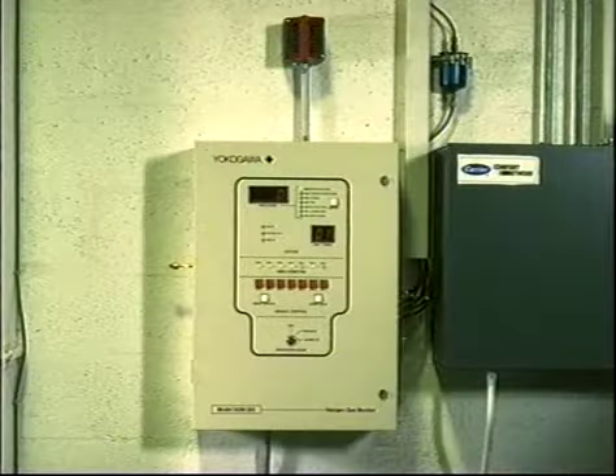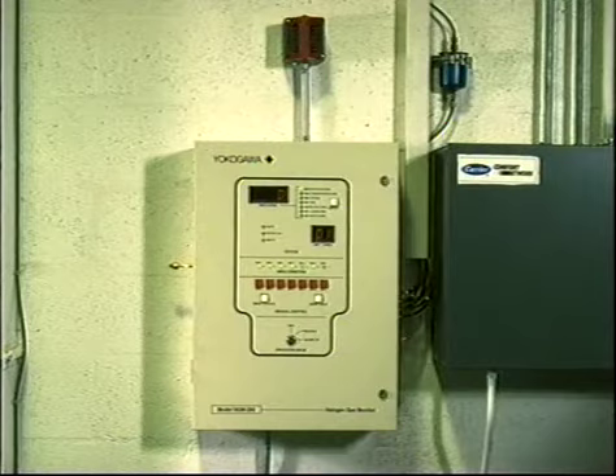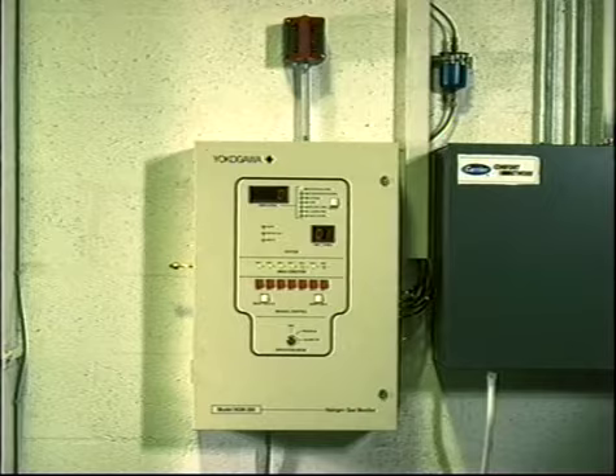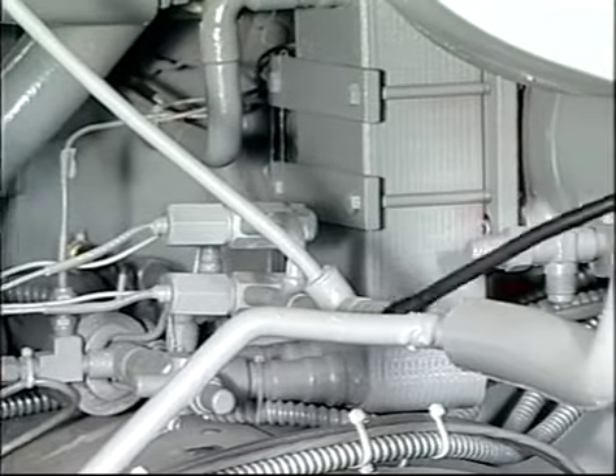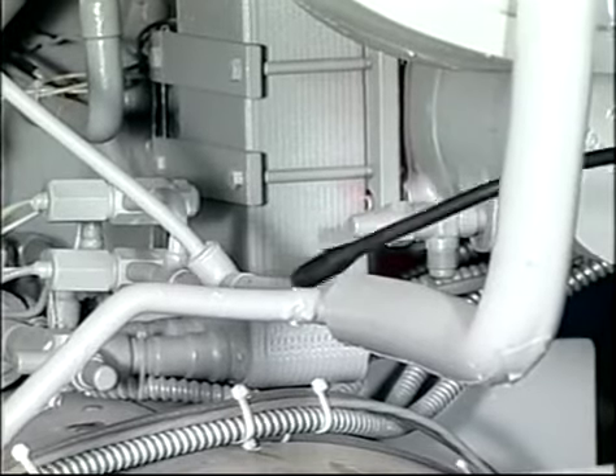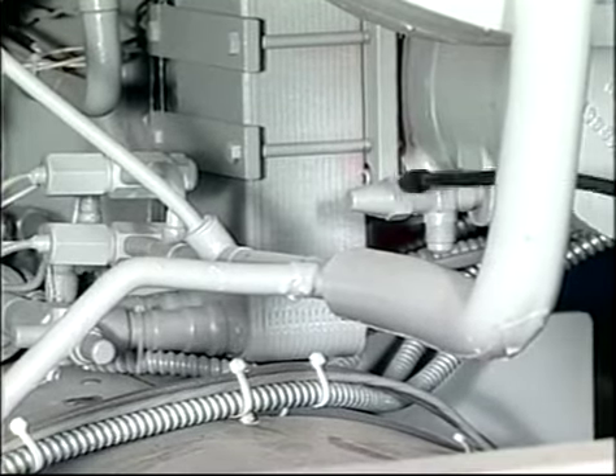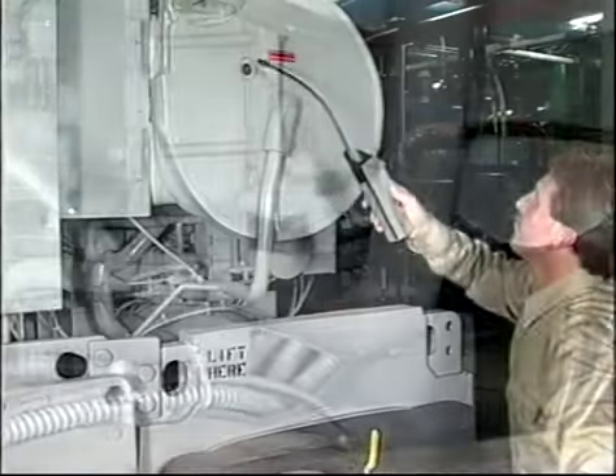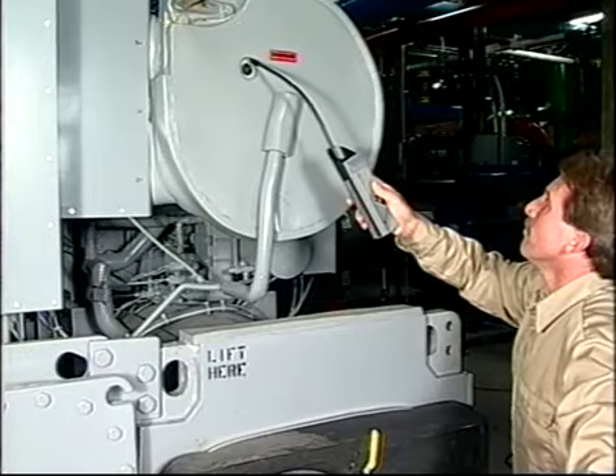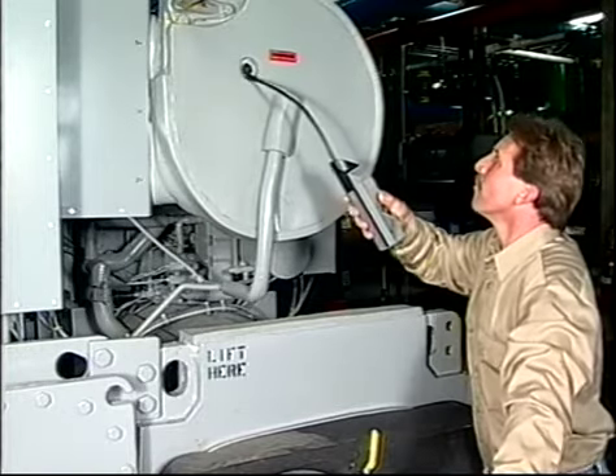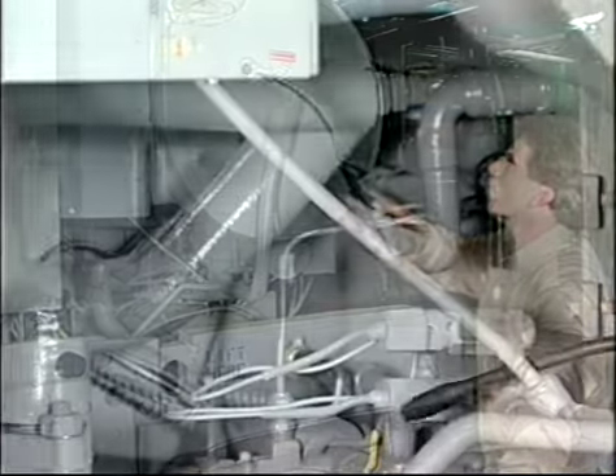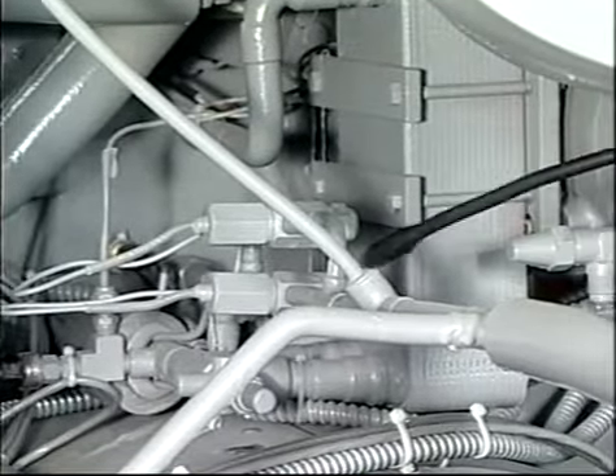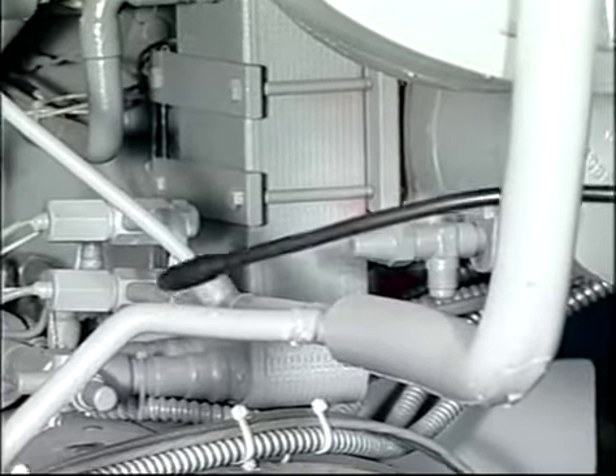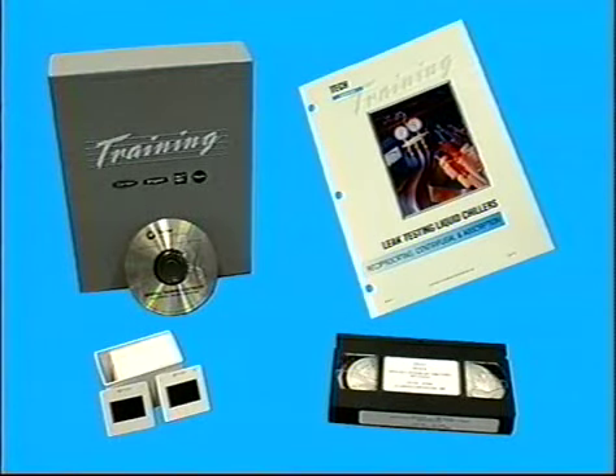If you have permanent leak detection equipment installed, be sure to monitor it and check to ensure it's working properly. Small leaks in high-pressure machines are sometimes visible before they are detected by instrumentation, because a small amount of oil may accumulate at the leak site. If the annual leakage rate for the entire chiller is greater than 10% of the total operating charge, the leak should be repaired immediately. If the total leakage rate is less than this, but greater than 1 pound per year, the leak should be marked and repaired during annual maintenance. A new training program for leak testing liquid chillers is now available. Refer to the workbook appendix for ordering information.